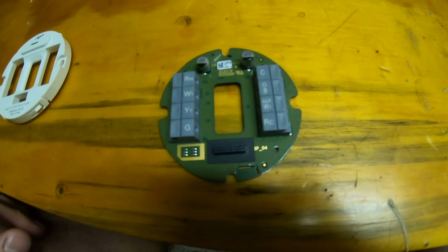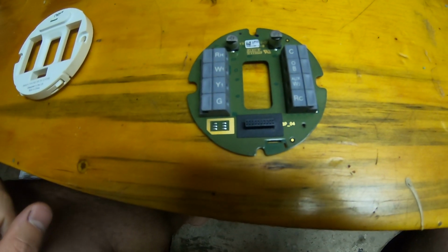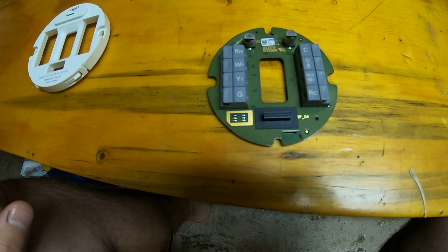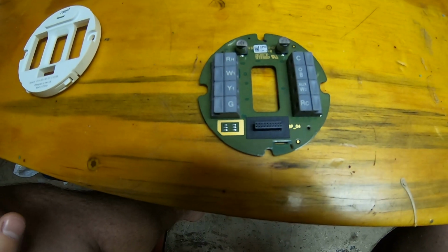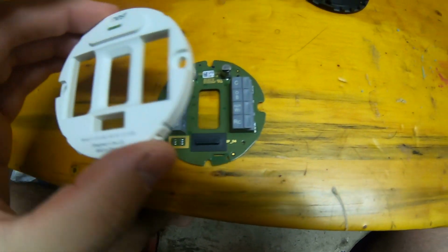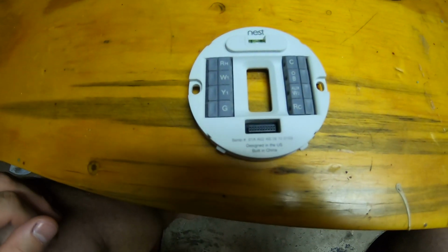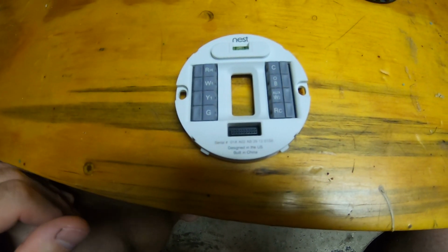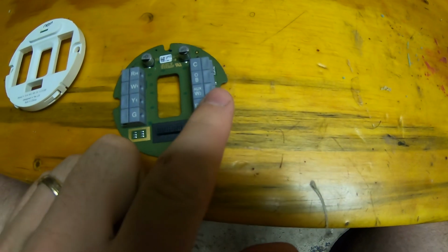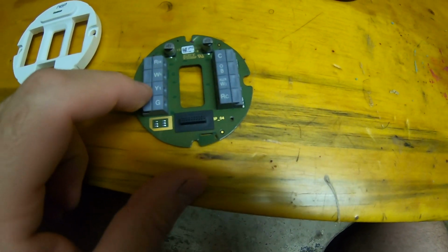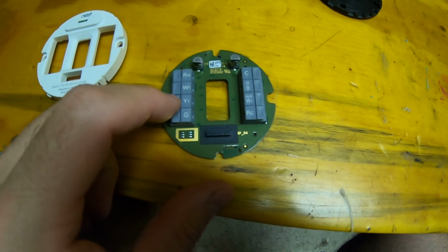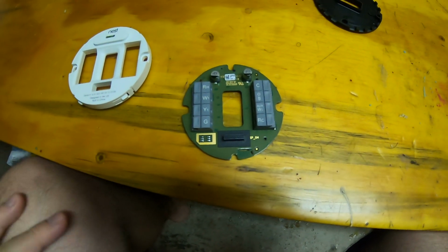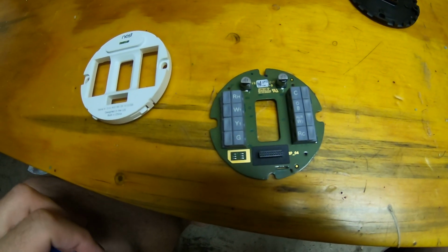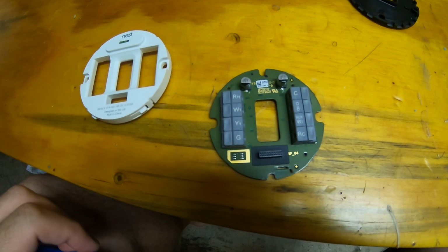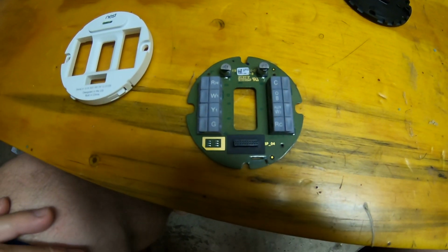So long story short, if you see any weird behavior at the contactor when the system is calling for cooling, low voltage situations, or just otherwise odd behavior, and you have a Nest thermostat, especially a first generation, you might want to dig a little bit deeper into that thermostat. You could try jumping, again, the R to Y1 to see if you then get 28 volts at the contactor. I'd recommend doing all this obviously with either the disconnect pulled or the breaker for the condenser tripped, just so you're not cycling that thing on and off.